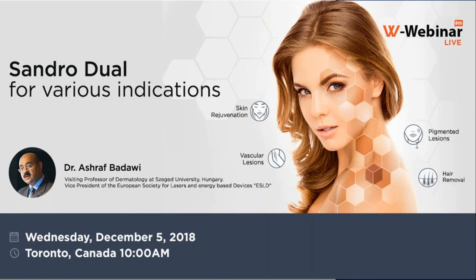If I reduce the spot size, should I adjust the fluence? No — because we are using fluence in joules per centimeter squared. Whether using a 20 mm or 15 mm spot, fluence should not change because the machine adjusts so that the output is the same joules per centimeter squared regardless of spot size.